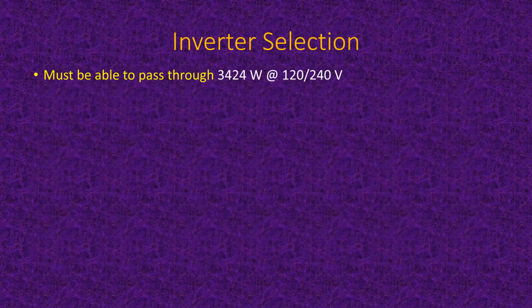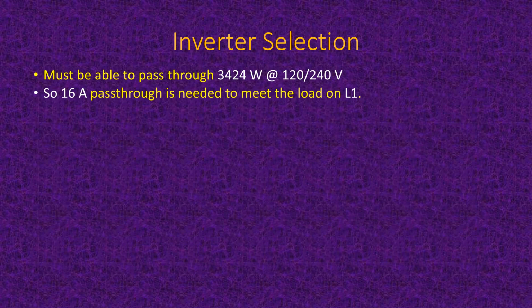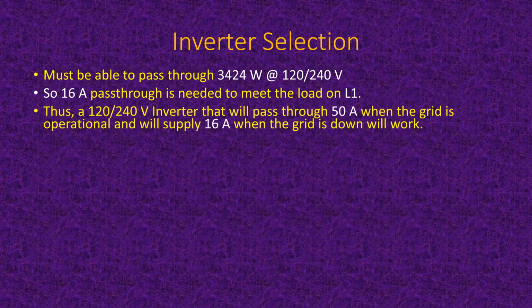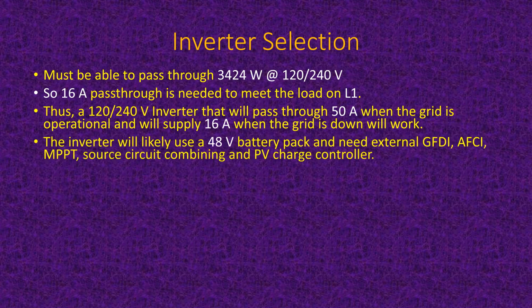Okay, so now we need an inverter, and remember back there we needed at least 3,600 watts, or 3,424 watts. It has to be able to pass this through from the utility when the utility is up and it's nighttime. It needs to be able to pass through 16 amps to meet the load on line 1, a little bit less on line 2. So we look for an inverter that will pass through 50 amps, because that's what most of them will do when the grid is up, and when the grid is down, supply 16 amps. Okay, so let's see what we might find.